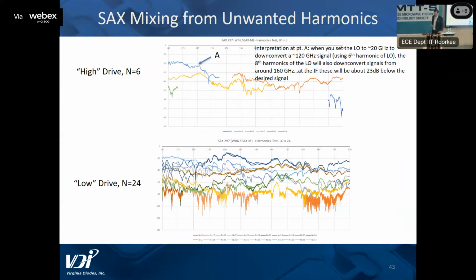Again, the disadvantage of working up from RF microwave, as opposed to coming down from an optical regime, is you do have to deal with all those harmonics of that lower frequency. That applies both in receiving and in transmission, meaning you do get some mixing off these other unwanted products. So we have to be very careful to do filtering at every stage. We characterize this in our extenders, looking at the conversion from these unwanted harmonics, and try to limit that to 10 or even 20 dB below the intended mixing product. But it is a very difficult process.